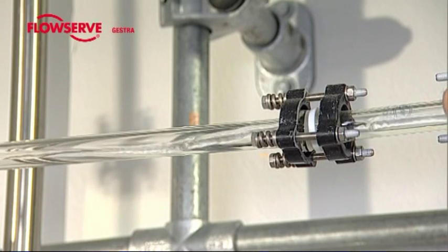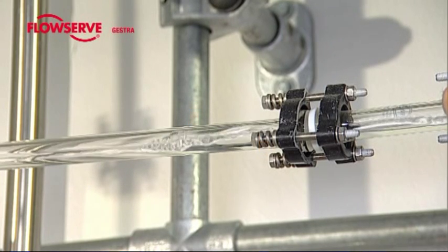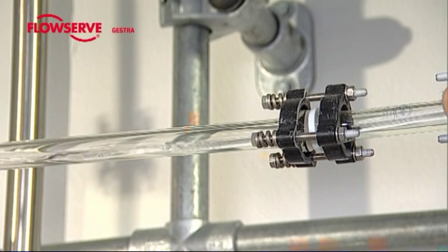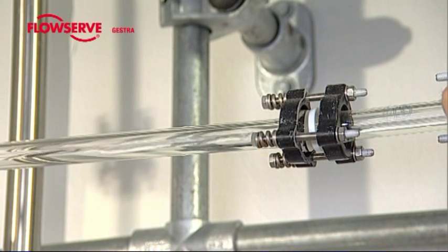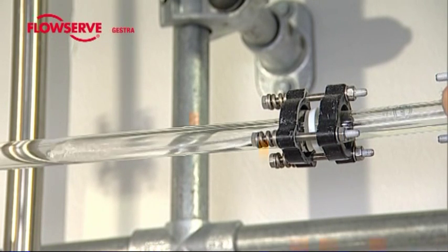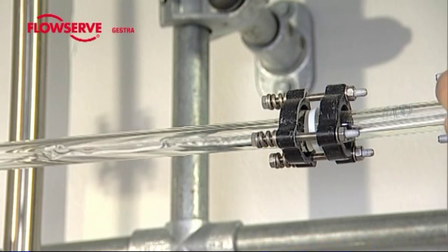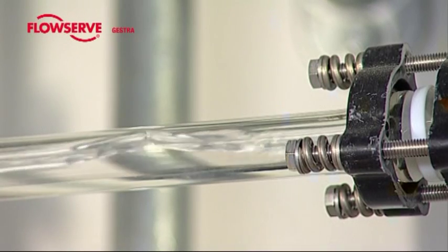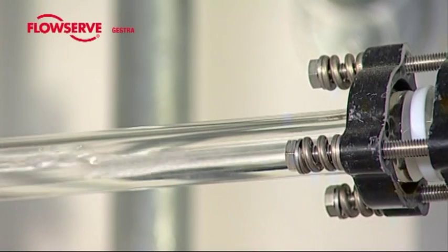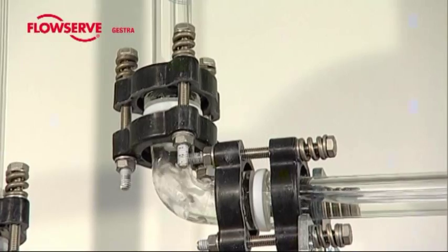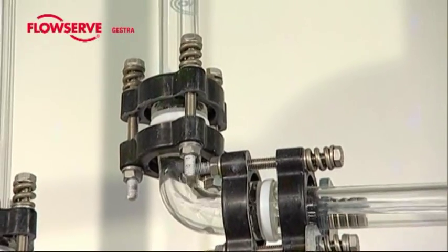The water attempts to fill this vacuum as quickly as possible, collapsing into the empty space. The water quantities accelerated in this way must now be stopped in fractions of a second. It's possible for pressure shocks with peak values of more than 1000 bar to be created. This becomes noticeable through the visible shocks and explosive sounds.